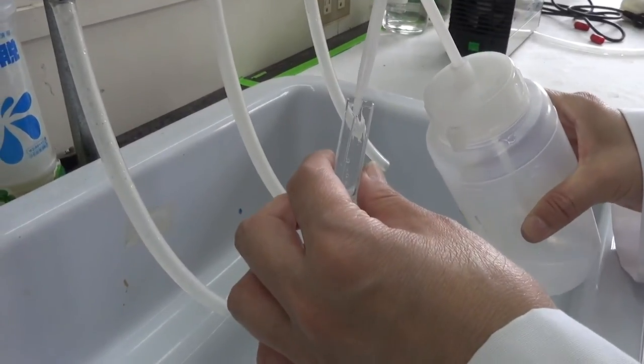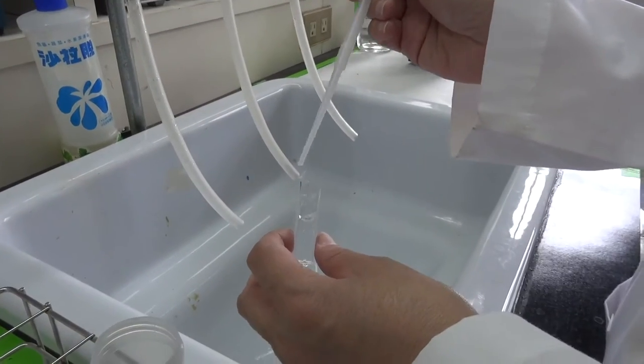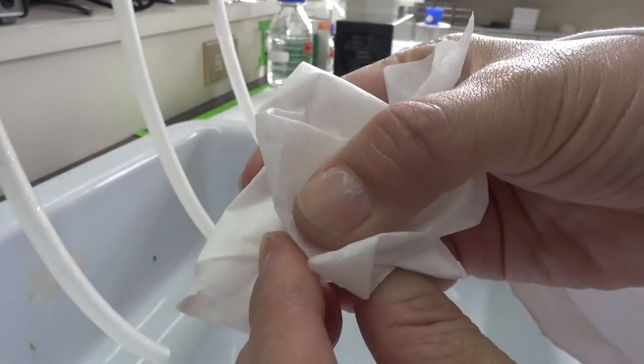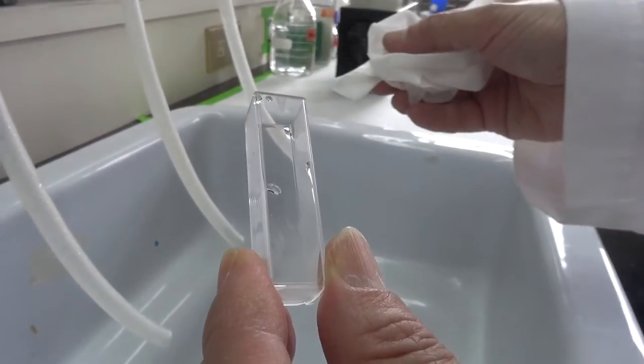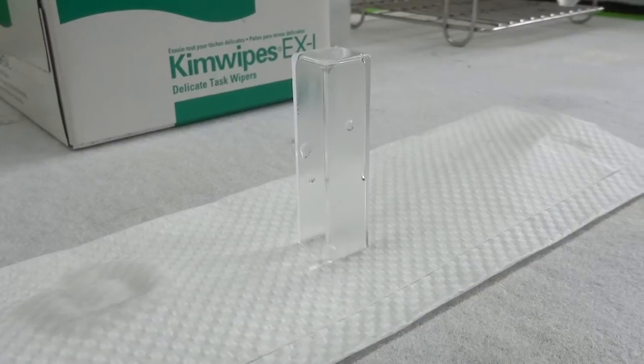Before and after use, please be sure to clean the cuvette thoroughly. Rinse the inside with distilled water a few times and wipe the clear light passing sides carefully with a Kim wipes. Leave the cuvette upside down on a paper towel to dry before next use.